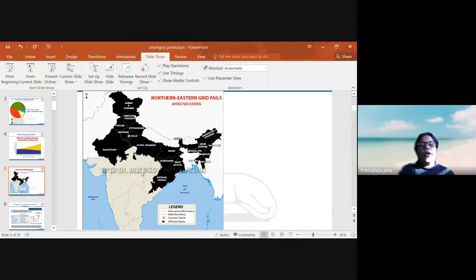So this heavily loading condition, we call in electrical engineers, load encroachment problem. That line was heavily loaded, and due to the heavy loading of the line, one of the distance relay zone 3 has been tripped.